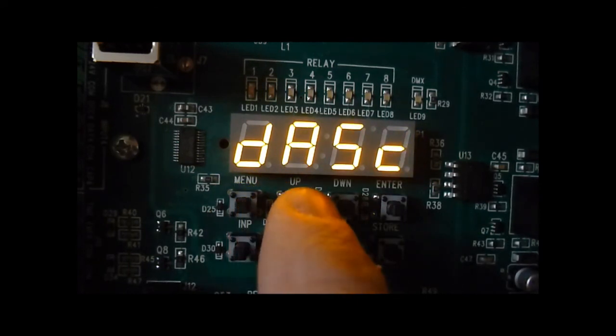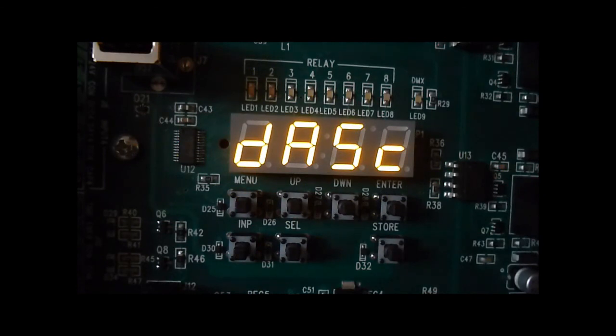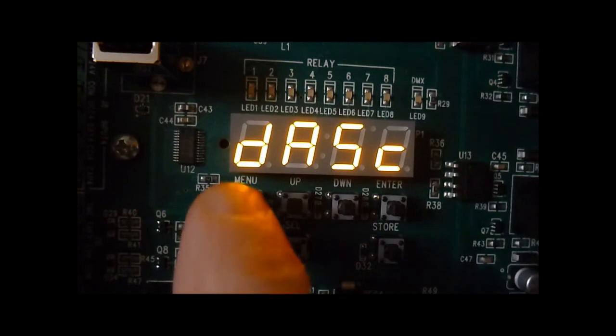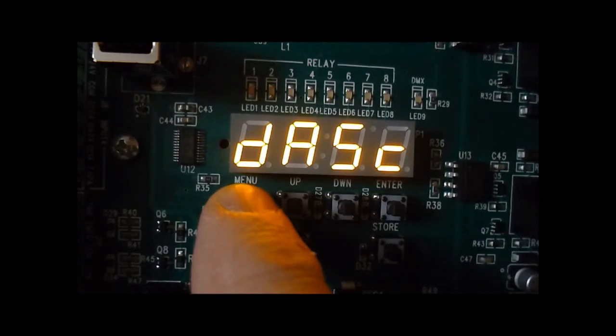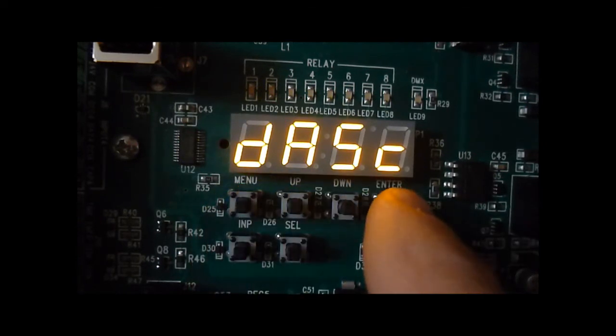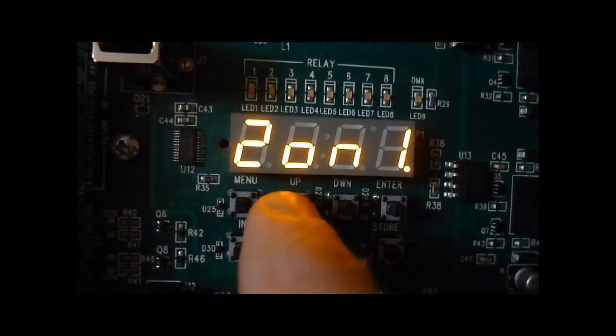And lastly, the daylight scaler, which is a primary secondary zone daylight adjustment. What this does is allows one photo cell to control more than one sensor and scales the effect of the photo sensor on any zone that's assigned to a daylight sensor. Press enter and we can scroll through all the zones on the relay panel - one through four on this system, or one through eight on an eight circuit system.